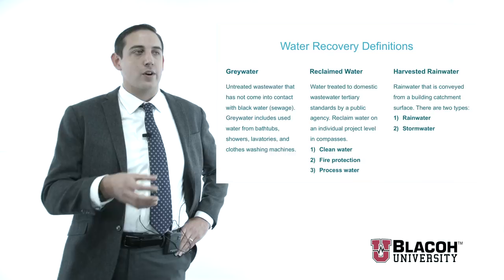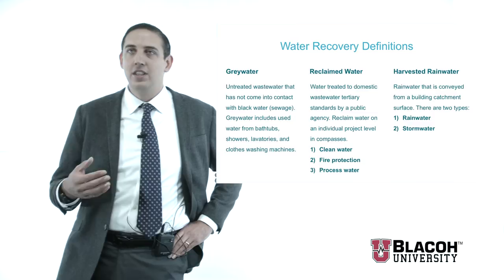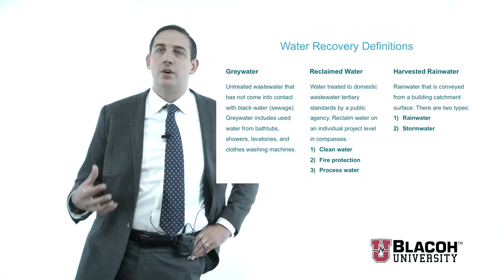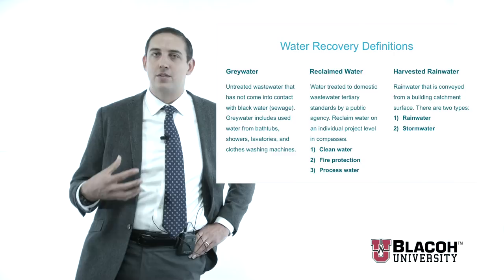The two we focus on predominantly here in the United States are reclaimed water and harvested rainwater. Reclaimed water, which is also identified sometimes as clean or clear water, is water from such devices as HVAC condensate, reverse osmosis reject, and fire protection waters — waters that have been used but have picked up very little if any contamination from these different sources.